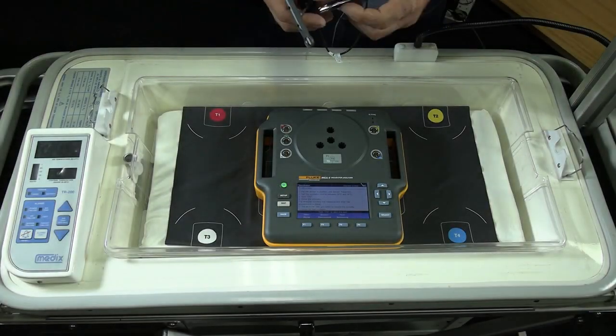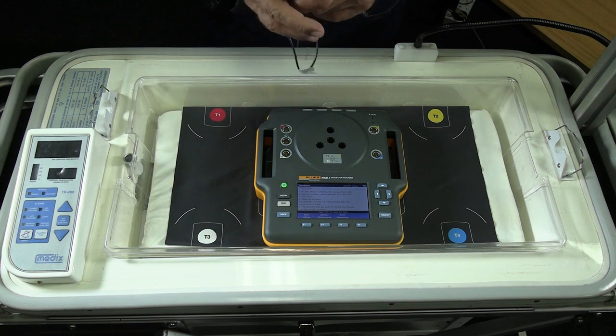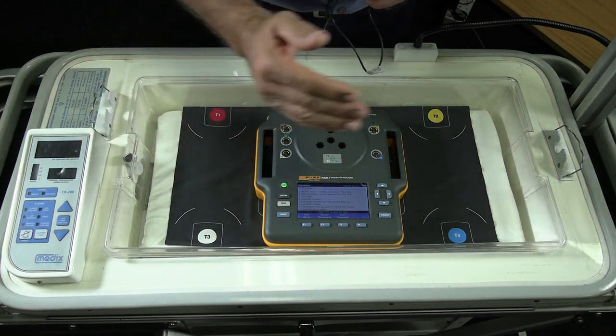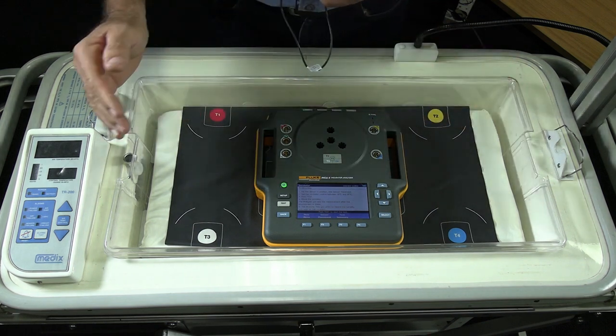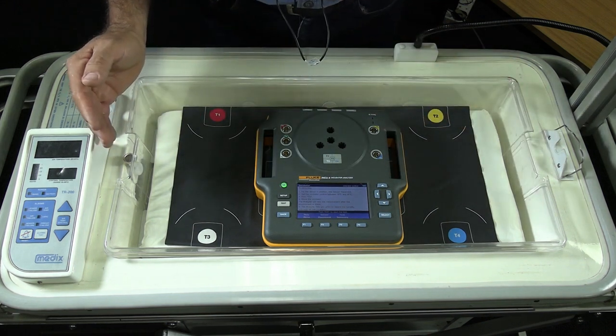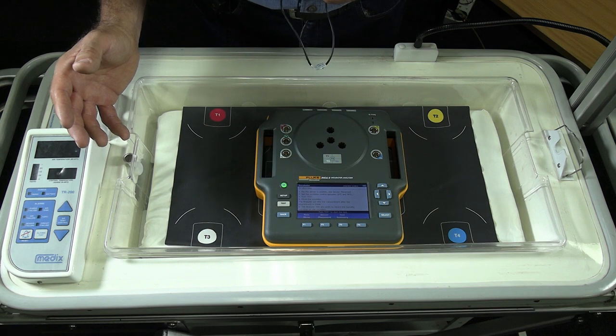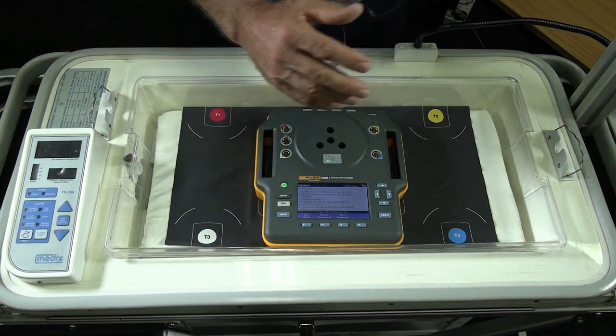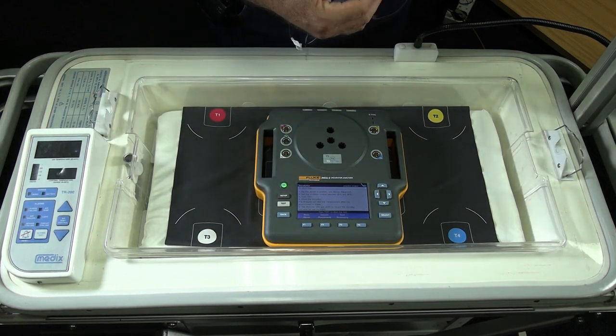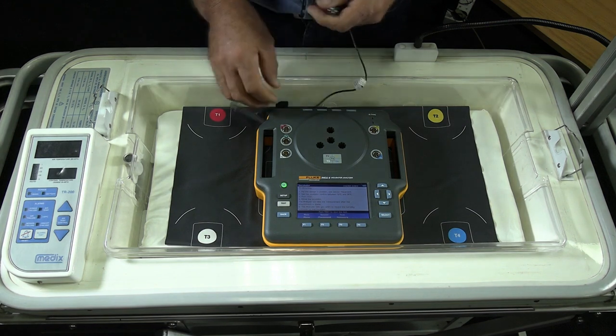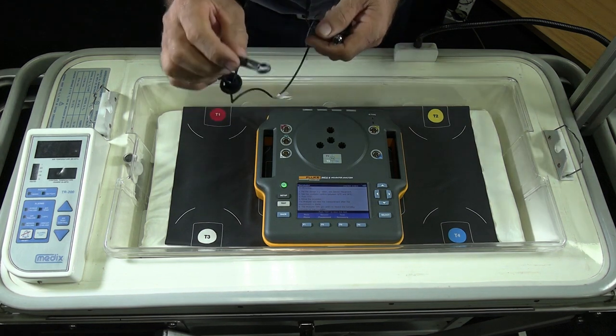Airflow testing: what we want to do is make sure that the airflow from the fans on the inside of the unit, the airflow that goes across the baby, is not too high or too low. This airflow from the fan is what carries the temperature and the humidity across. So in order to test airflow, we make use of an airflow sensor.